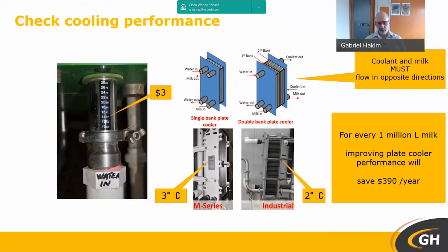But we've seen these things not work very well. Milk goes into about 26 or 27 degrees. Most of the time we found that instead of 2 degrees, instead of 3 degrees, it's more like 6 degrees difference or 7 degrees difference. So for every million litres of milk, if you just did that, you'd save almost $400 a year. So if you're doing 3 million litres of milk a year, just by doing a simple improvement here, you save around $1,200 off your electricity bill.